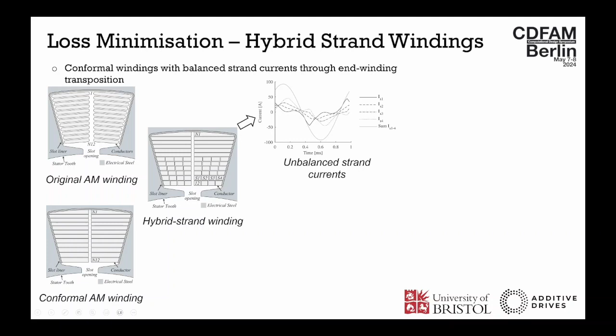So we have this segmented conductor: solid conductors at the top, segmented conductors at the bottom. This creates a phenomenon where we get circulating currents between the individual strands, which additionally leads to AC losses. So although we've reduced the losses, we can reduce them further if we get rid of these circulating currents.